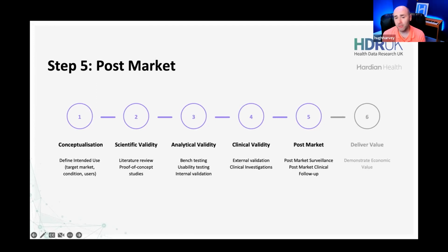But you are a medical device manufacturer. You are mandated by law to monitor the performance and safety of your device forever while it is on market. And these documents must be continually updated through the practices of post-market surveillance and post-market clinical follow-up. You will be audited on an annual basis at minimum, and you can have random unannounced audits from your regulatory auditors as well.